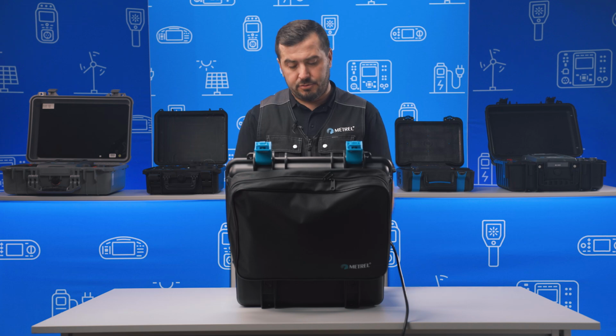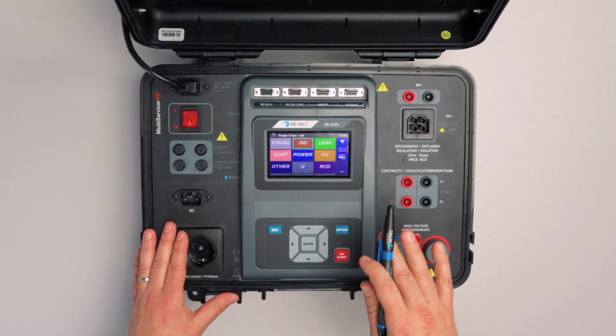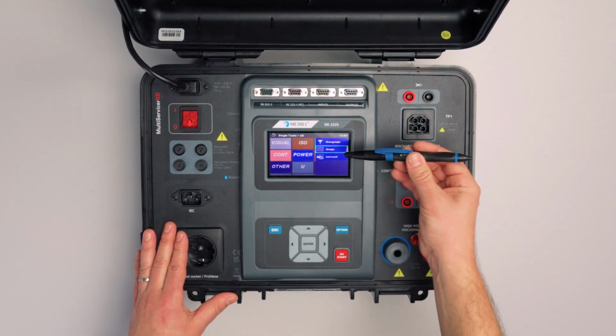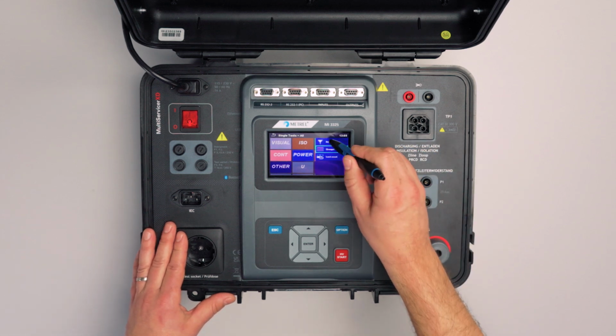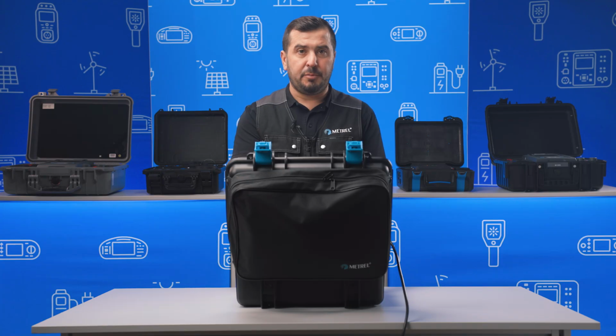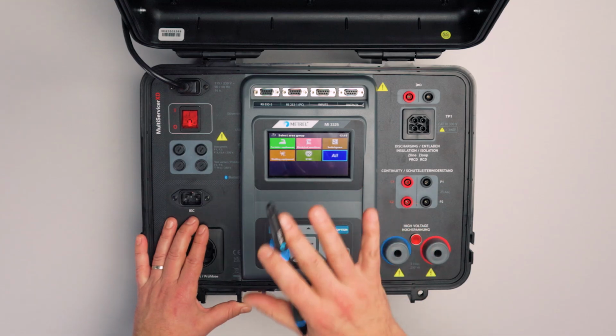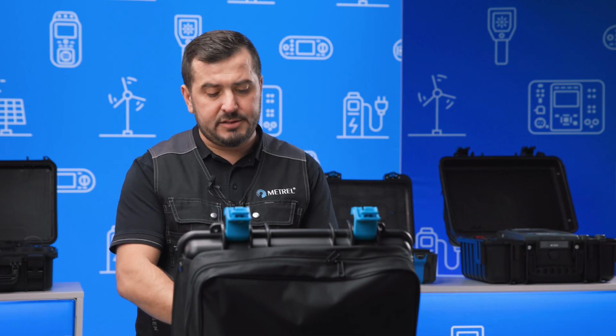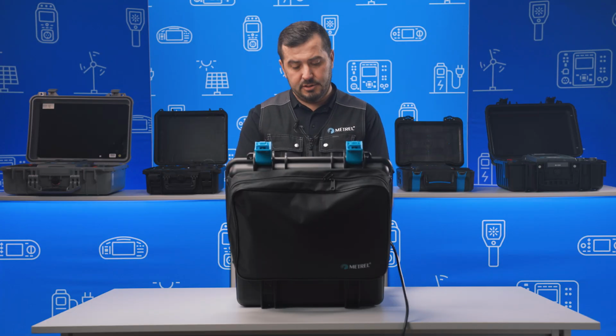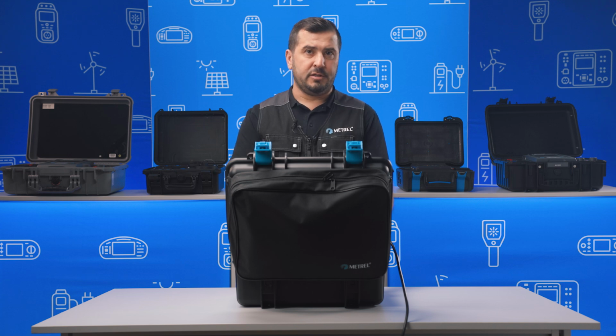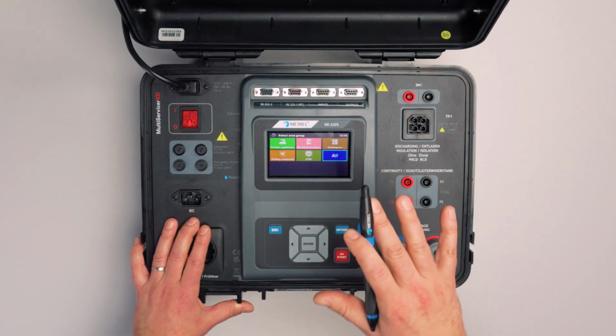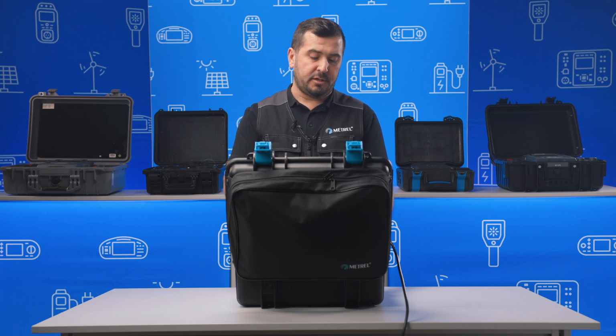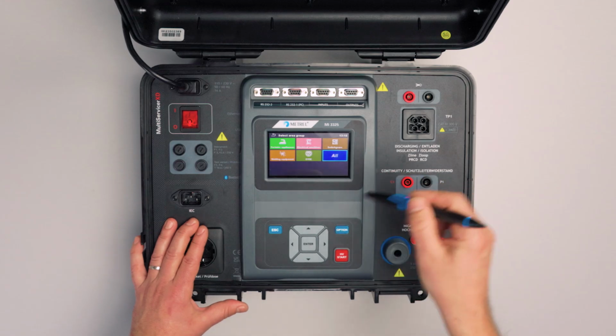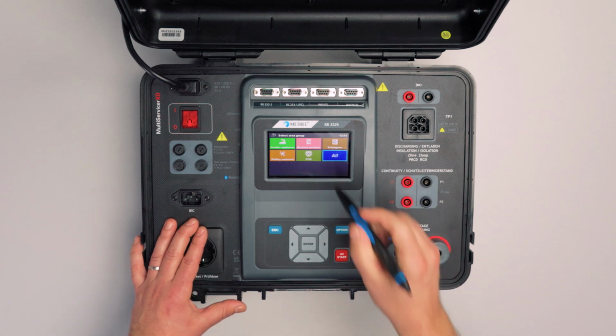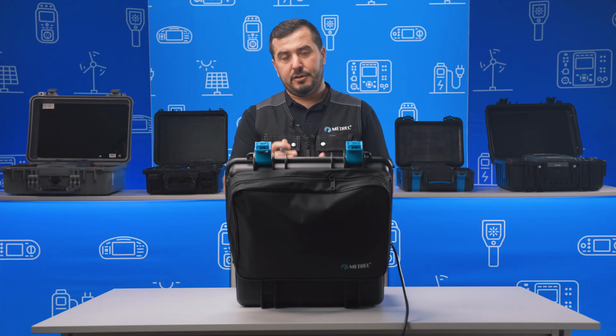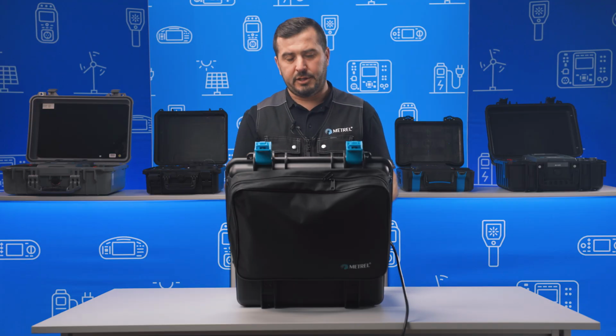So now let's focus on the single test menu. Inside the single test menu, you can firstly notice that we have a special filter, which is called area groups. If we select this filter, we can see the applications that are supported by the instrument. The instrument supports testing of electrical equipment, or let's say portable appliances, then electrical machines, switchgear, welding equipment, and also electric vehicle safety equipment. So all of these area groups are covered by the device, and in case we are performing tests on just a specific application, we can simply choose one of these options, and the instrument will list only the measurements that are applicable for that specific application.